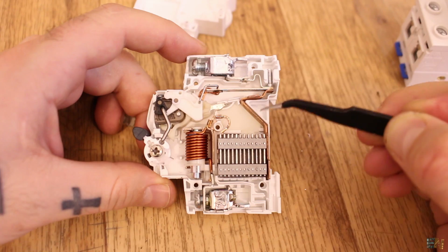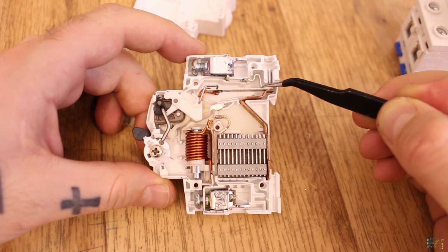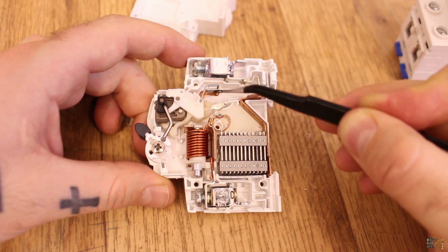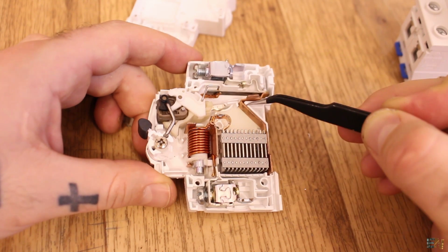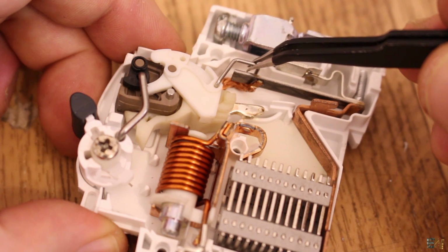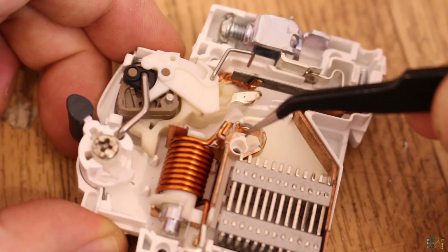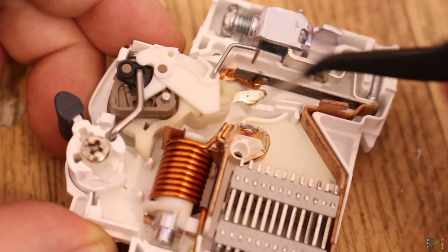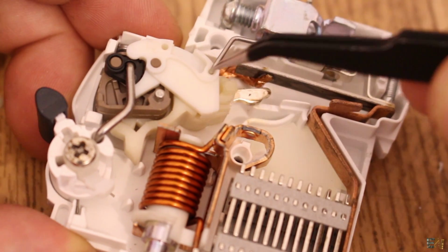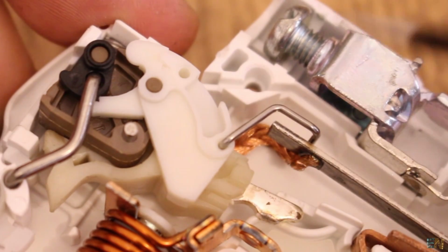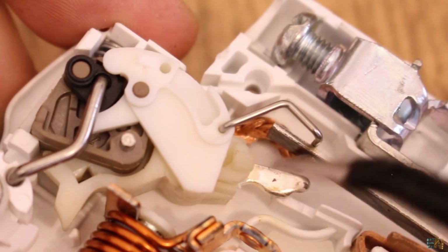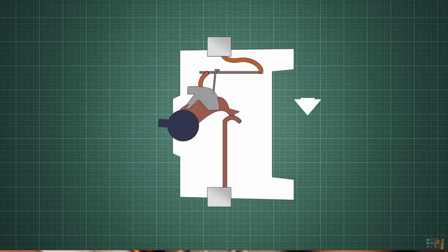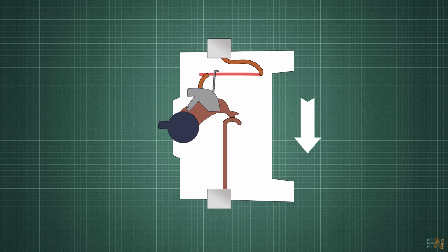When a metal heats up, it will change its shape due to metal dilatation. A very small shape change is enough to push this small lever up. And look what happens when I pull the lever up. Yes, the entire actuator will just jump and open the circuit. That's because this lever is connected to this plastic part of the actuator. And when we pull it up, it releases the tension, and since we have a spring below, it will pull the actuator away. So that's how the thermal protection works. We have too much current, the metal strip will heat up and change its shape, that will give a push to the lever up, and by that releasing the actuator and interrupting the circuit.